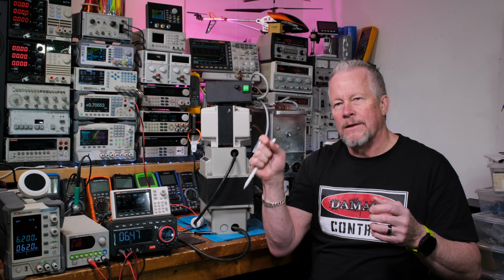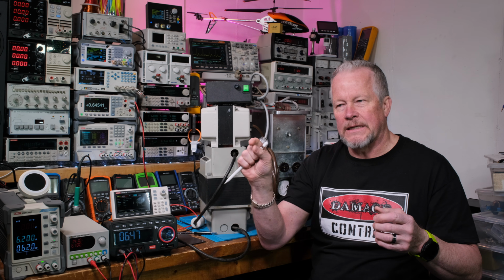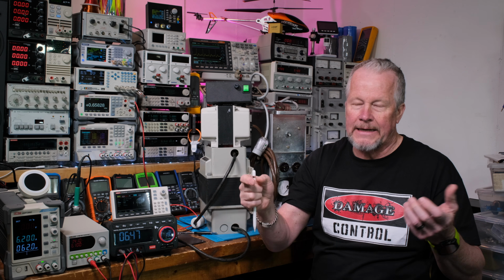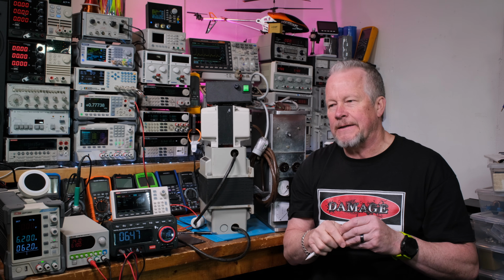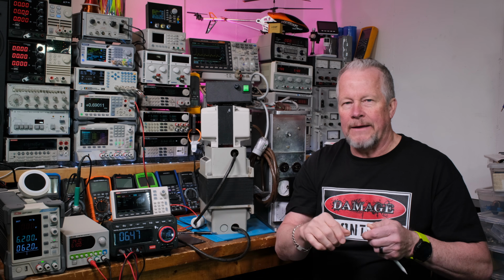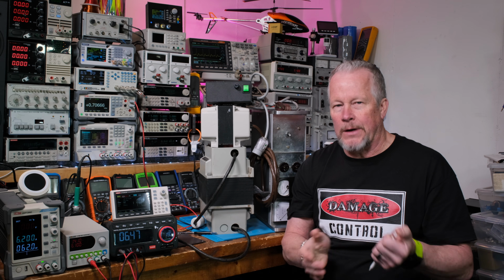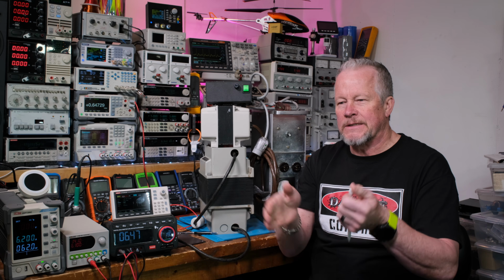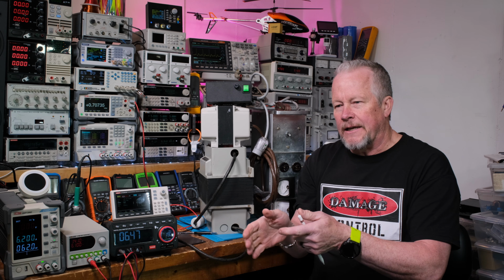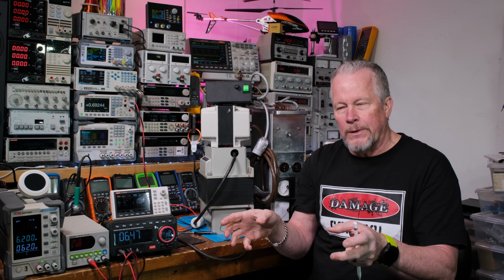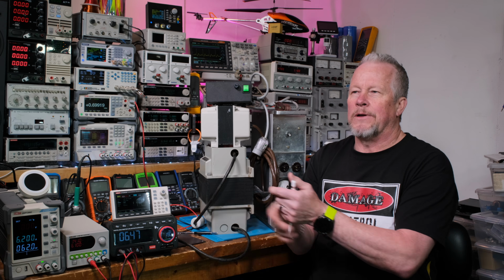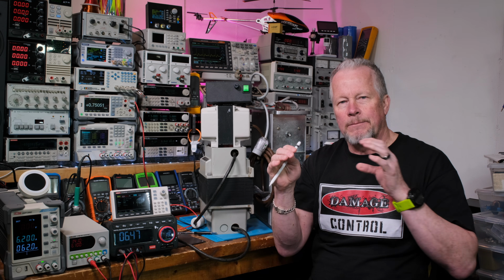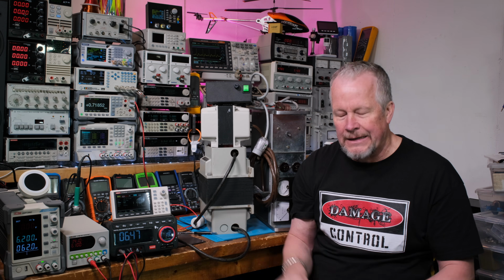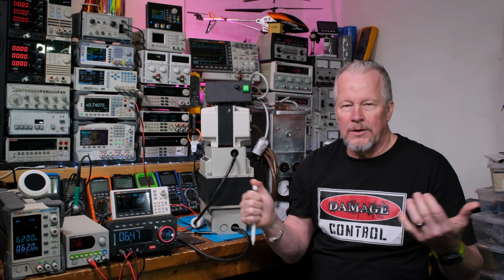If they bond one of those winding outputs on the secondary side, like the X2 terminal, to the chassis, and recreate that bond point from your service entrance, it's because they say, okay, we isolate it, but we isolate it for noise or other reasons, while still wanting our ground and neutral to be bonded together. So if there's a reason they did that, you want to be aware of it.